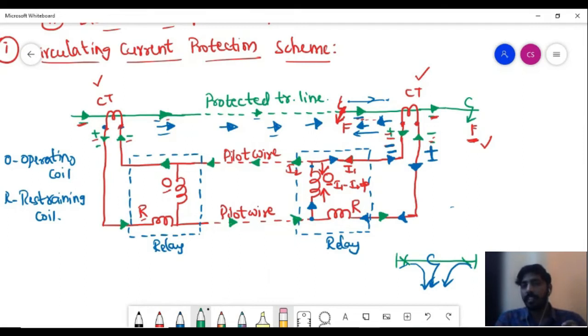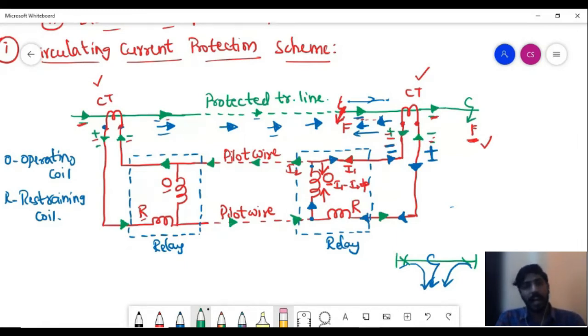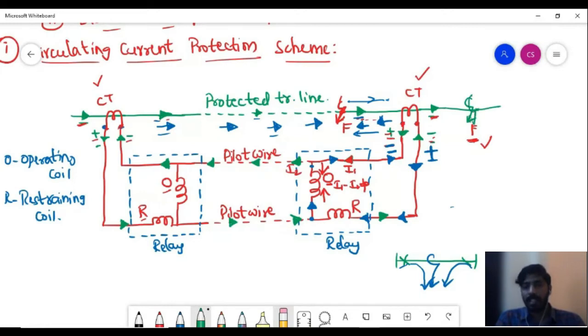I have not changed the direction of the CT placed at the sending end — it remains in its normal direction. Only the CT placed at the receiving end has its current direction reversed, because the current direction at that CT location is reversed as it tries to feed the fault. This reversal is not possible if the fault is outside the protected line. If the fault is external, the current direction at the receiving end CT still does not reverse, so the protection scheme does not operate.